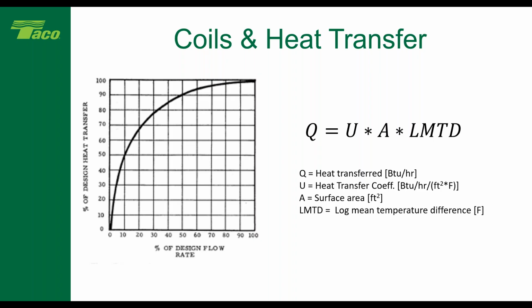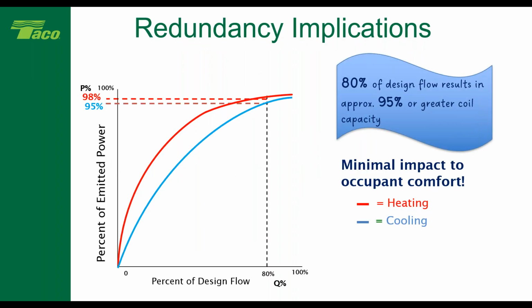So if you look across the horizontal axis, that is the percentage of design flow rate. If I look at 80% flow, I'm up above 90% of heat transfer. So what that really means is that for a heating coil, at 80% flow, I can get 98% of the heat transfer out of that coil. And at 80% flow, I can get 95% of chilled water coil capacity. Now, we understand that HVAC systems are part load systems.